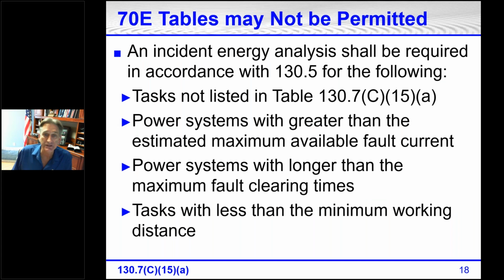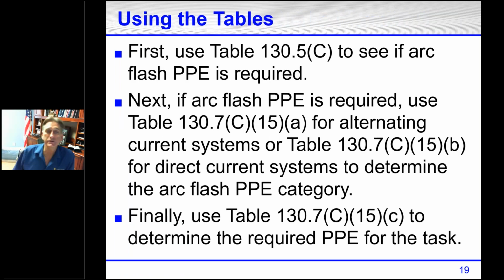An incident energy analysis shall be required in accordance with 130.5 for the following. What this means is that you have to do an incident energy analysis if the task is not listed in this table, if the power systems have greater than the estimated maximum available fault current, if the power systems have longer than the fault clearing times listed in the parameters, or if the working distance is going to be less than 18 inches. So we're going to look at table 130.5C to see if arc flash PPE is required. Then we're going to go to these other tables, and if it is required and we're able to do it, then we're going to look at the PPE category table in order to select our arc rated PPE.